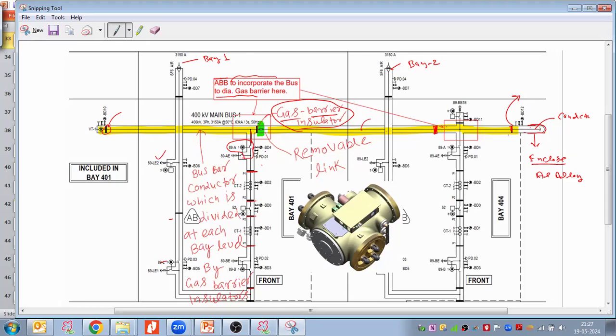Now if you see this much, could you see the BD, these fittings? Yes, sir. These are the fittings that we discussed: gas density monitor, PD, gas filling valve. All these fittings are in each and every module, because each module is gas proof. So everywhere they have to provide them.